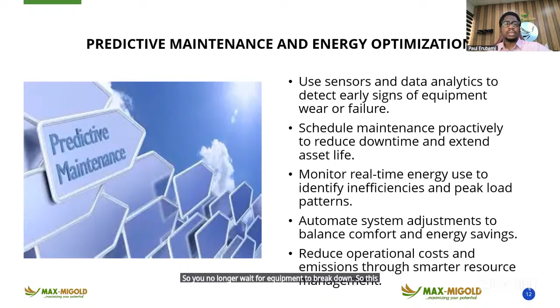So when people are off from the building on weekends, I go check certain things. I can find where that problem is coming from just because I was monitoring the energy consumption of that one equipment. Imagine if all I have in that facility is just one aggregate meter for measuring all the energy used in that space - there's no way I can do predictive maintenance and save myself and my organization from all the disruptions that can come from sudden breakdown.